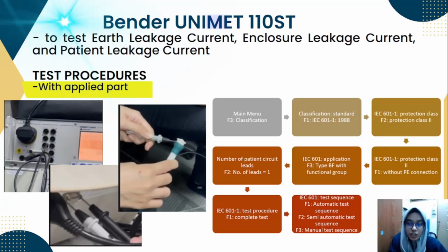Next, to test the earth leakage current, enclosure leakage current, and patient leakage current, we will use Bender with the applied part. Same as before, the Bender safety analyzer is turned on, then the 3-pin power plug of the tonometer is connected to the Bender, then we have 3 probes connected to the conductive part, earth of the tonometer, and the applied part of the tonometer. Then, the following options are chosen from the Bender monitor to conduct the test.